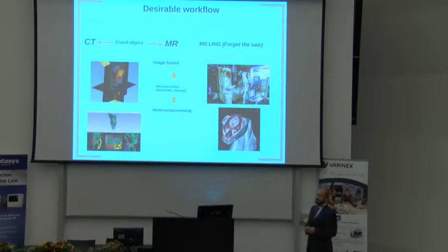It can be mainly done with manual reconstruction, because then you have to reconstruct all the things one by one, but you can also use the automatic image reconstruction from the CT and MR images, and then you can check on your manual images what you have done, or speed up your process a little bit. And then at the end you can have such images.